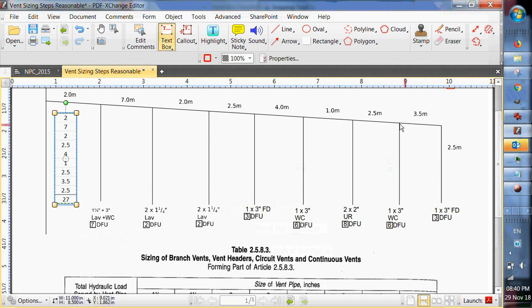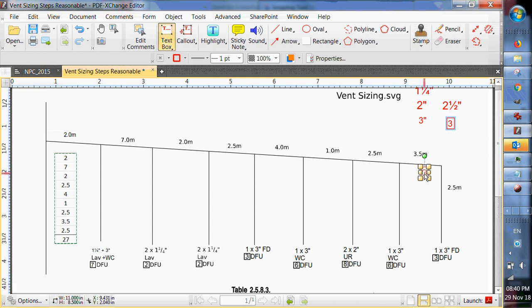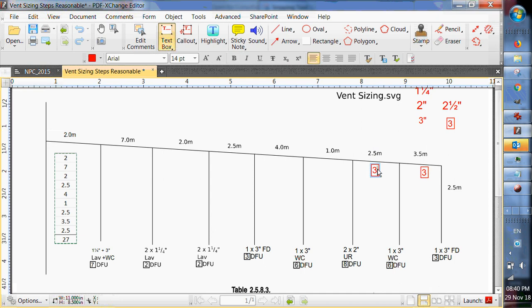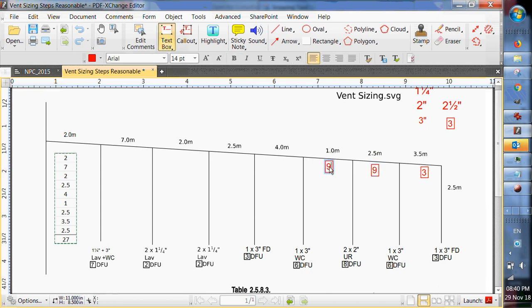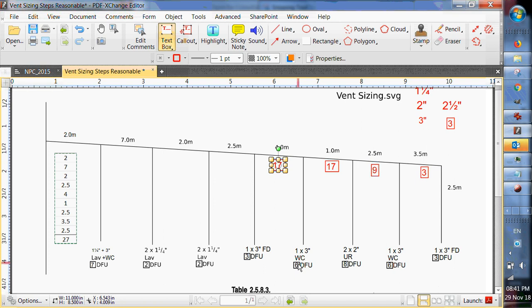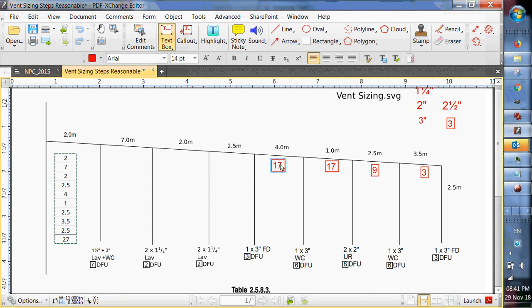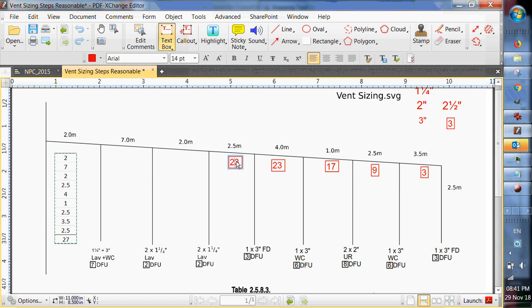So this one here is only going to have three fixture units on it. So three fixture units. The next one is going to have nine. The next one is going to have nine plus eight, so it's going to be 17. Add six to it. This is going to be 23. The next one we're going to add three to it, so it's going to be 26.